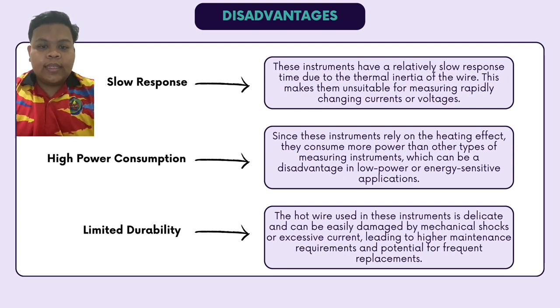The disadvantage of using hot wire type is slow response. These instruments have relatively slow response time due to the thermal inertia of the wire. This makes them unsuitable for rapidly changing current or voltage.